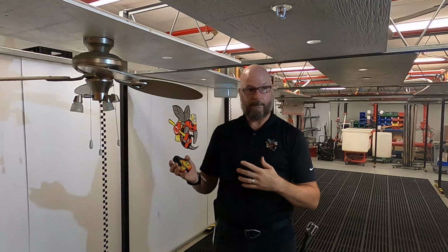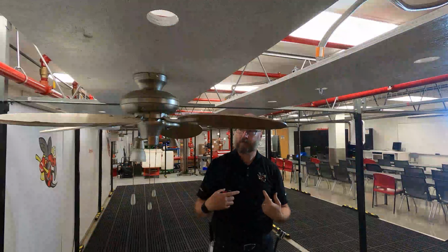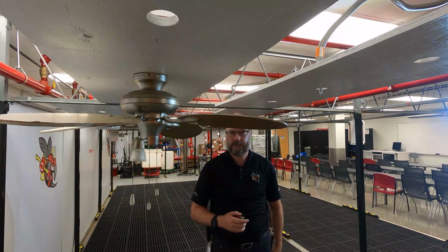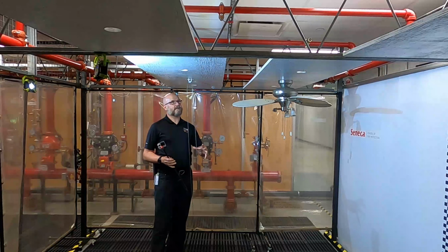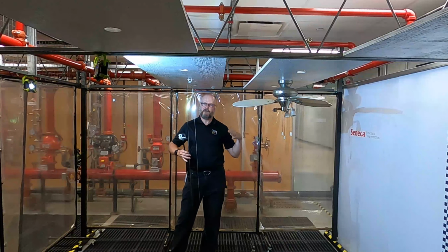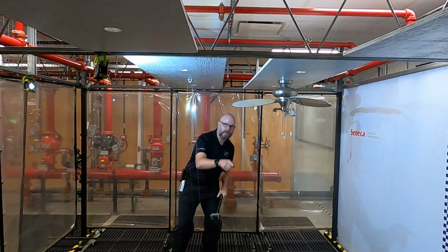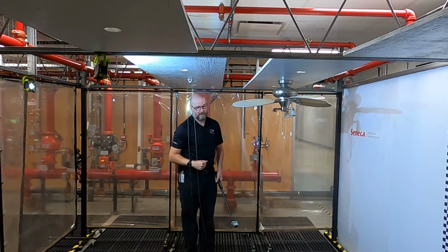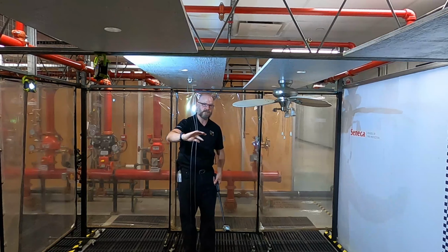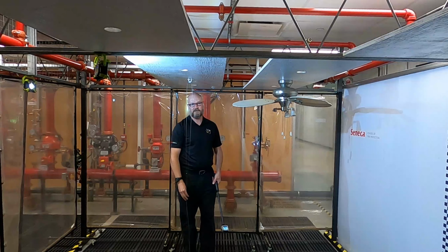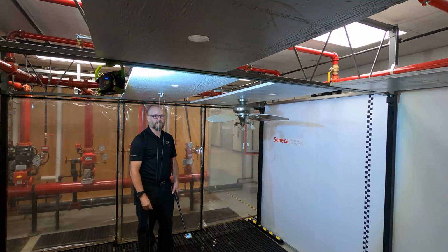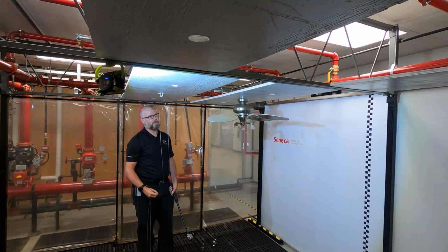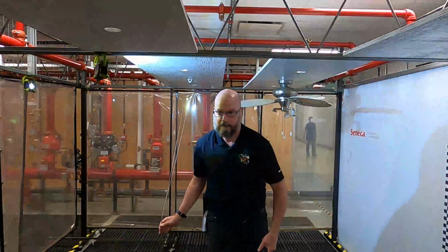That being said, I'm going to put up a couple barriers, and we're going to flow the sprinkler right now to see what this impact would be. So stay with me. All right, so we're set up with that same sprinkler head, same ceiling fan. Now we're going to get a little bit wet, and with camera angle number 1, camera angle number 2, and camera angle number 3, we're going to operate a sprinkler. I'm not going to get wet today, so we're using some stainless steel cable to operate the sprinkler, and we'll see what happens between this sprinkler head and the ceiling fan. Let's go.